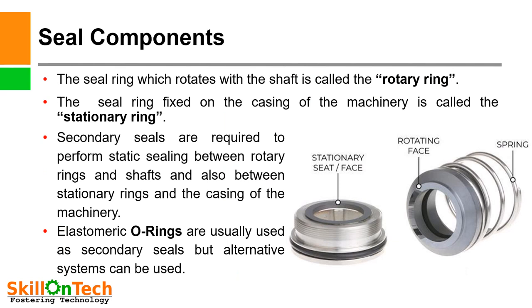The seal ring which rotates with the shaft is called the rotary ring. A picture of the rotating face can be seen here, accompanied with the spring. The spring provides pressure on the seal faces to mate with each other. The seal ring fixed on the casing of the machinery is called the stationary ring. Secondary seals perform static sealing between rotary rings and shaft, and also between stationary rings and the casing of the machines. Secondary seals are elastomers and O-rings. Elastomeric O-rings are usually used as secondary seals, but alternative systems can be used in place of O-rings.